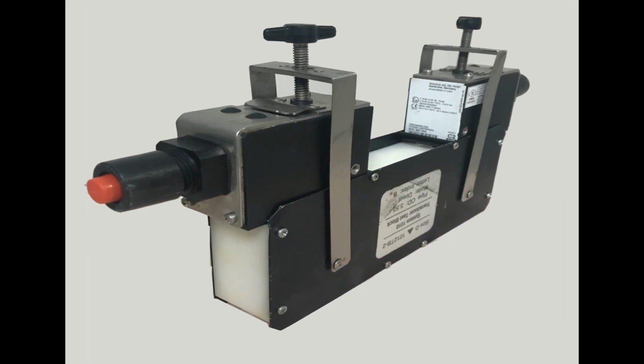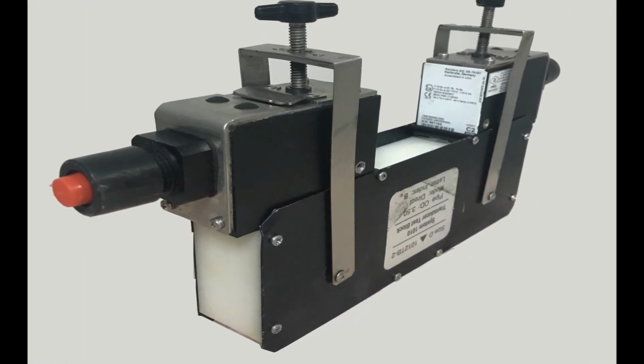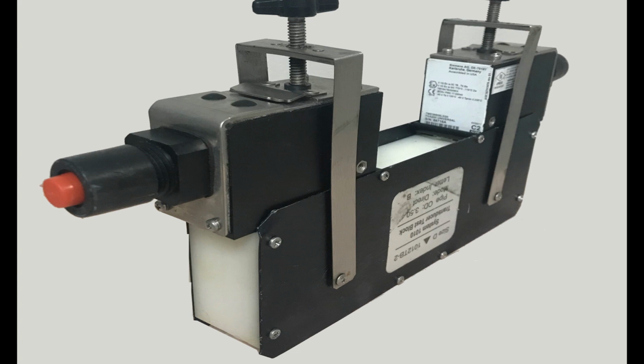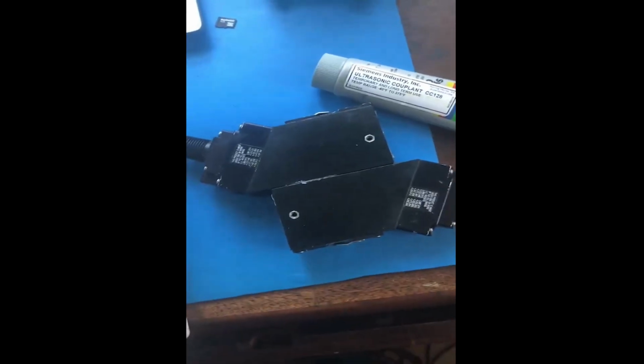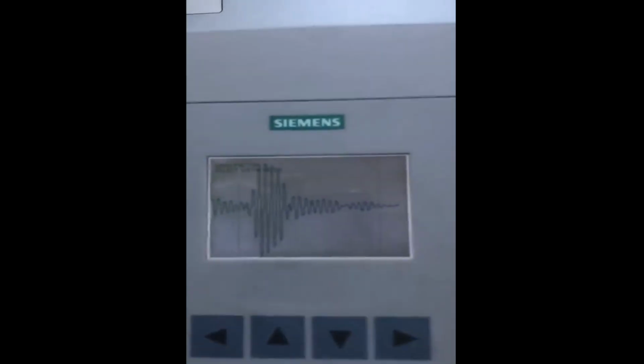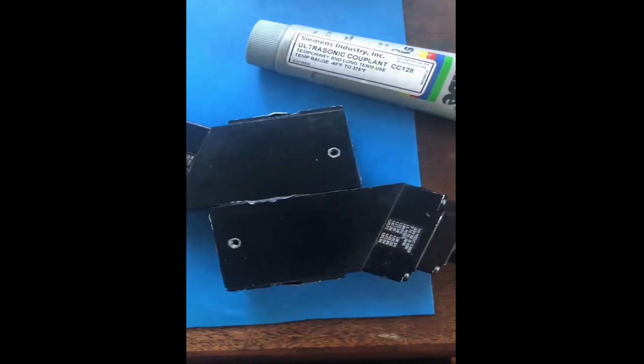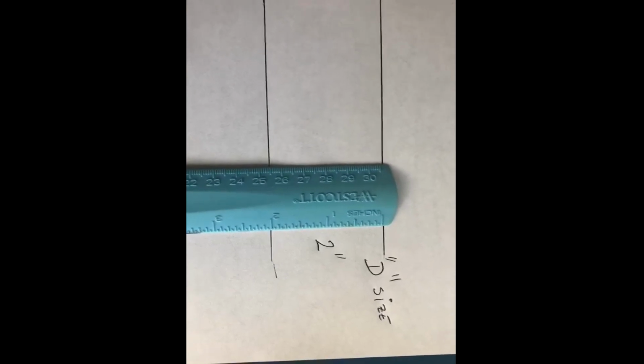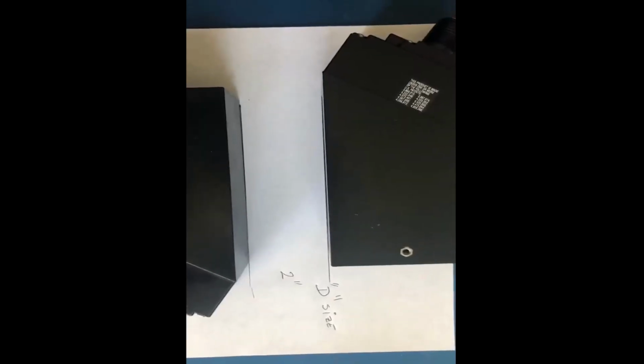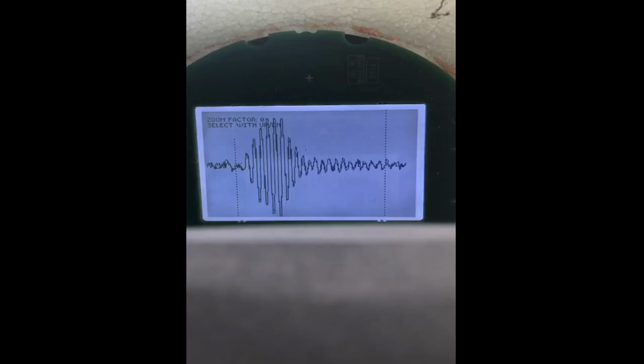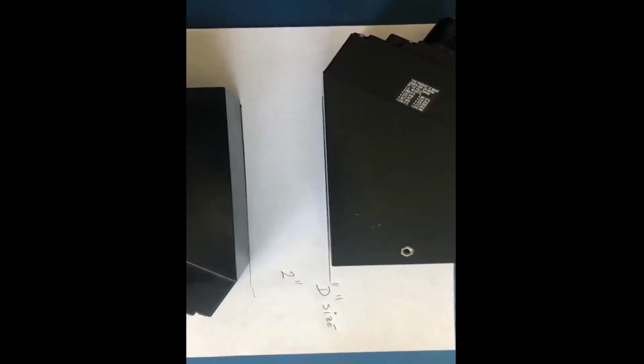For liquid meters, using universal sensors, Siemens offers test blocks on which you can install your sensors. Alternatively, you can perform a face-to-face test. Both methods enable you to test the flow meter system independent of the pipe and liquid. For gas meters, you can perform an air test to isolate the meter from the pipe. These procedures are explained in separate videos. I've put links to them in the video description.